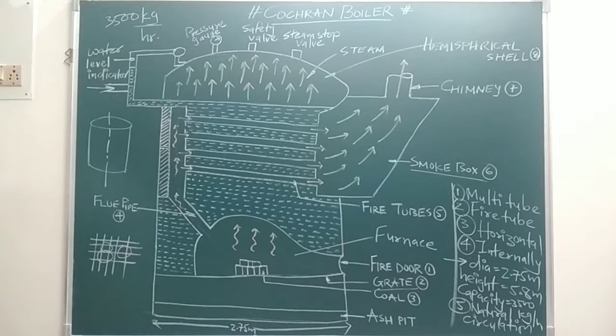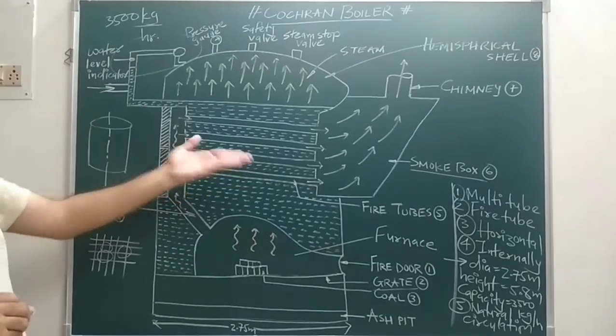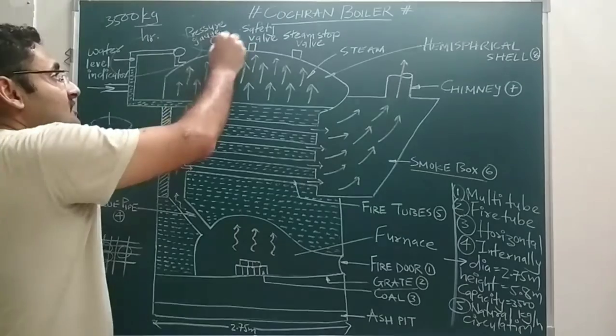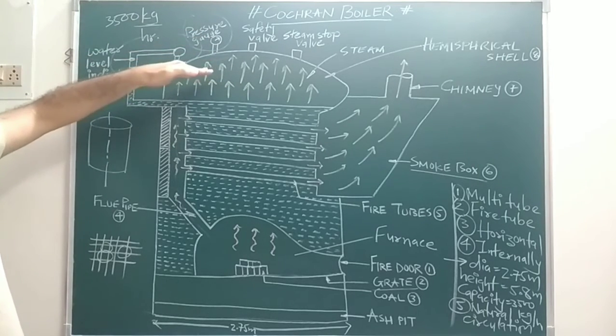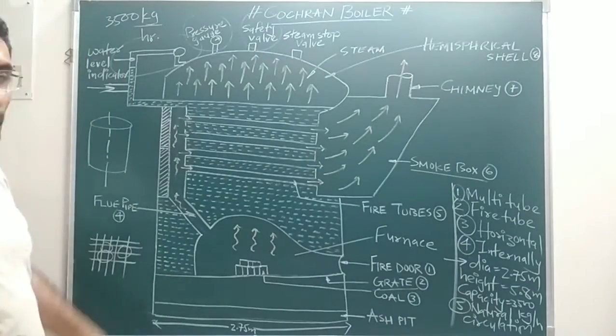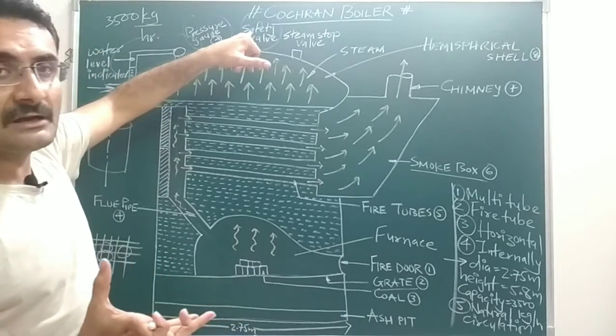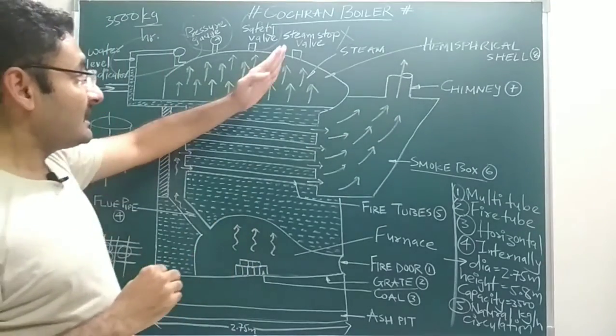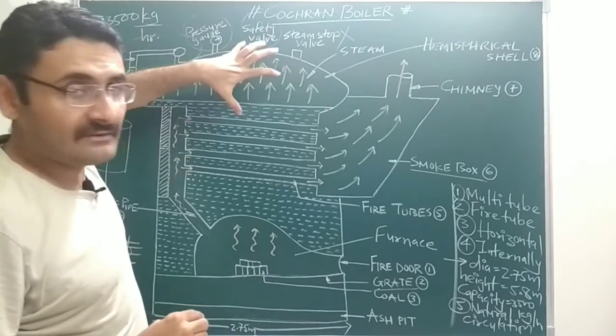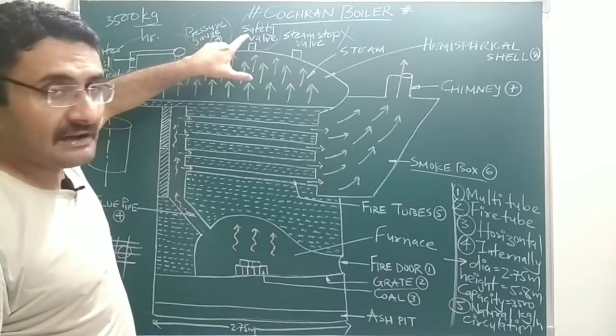Now we will discuss the mountings located at the top of the boiler. First is the water level indicator, which indicates how much water is present inside the boiler. Next is the pressure gauge, which indicates how much pressurized steam is present inside the boiler — for example, 20 bar or 22 bar. Next is the safety valve, which automatically opens when excess pressure is created inside the boiler, to avoid accidents.